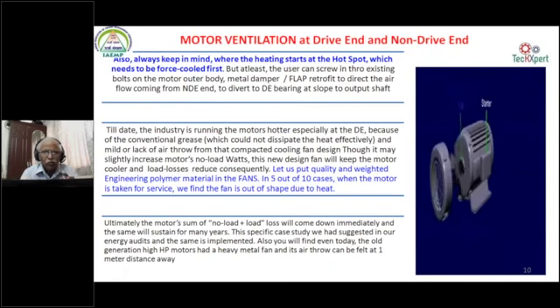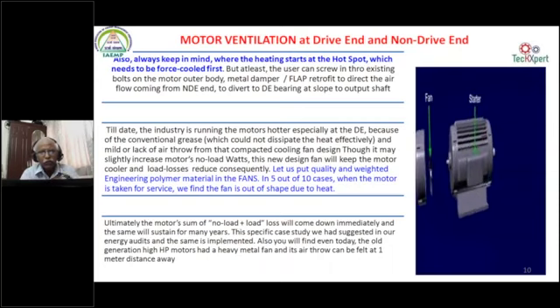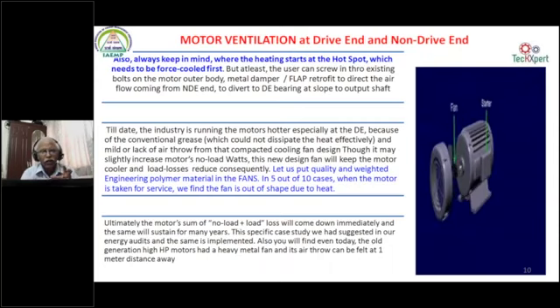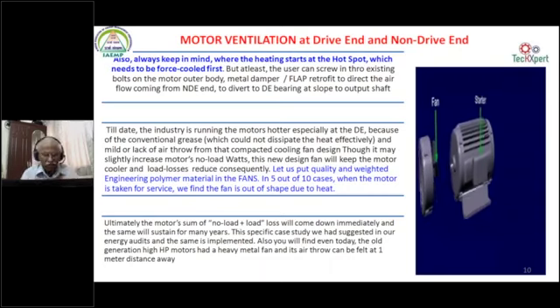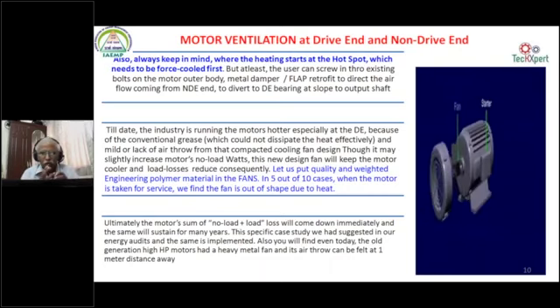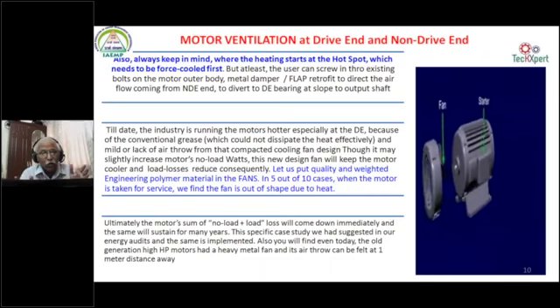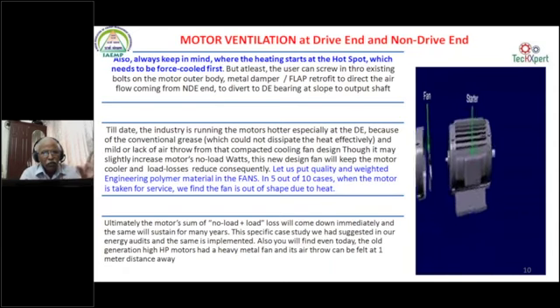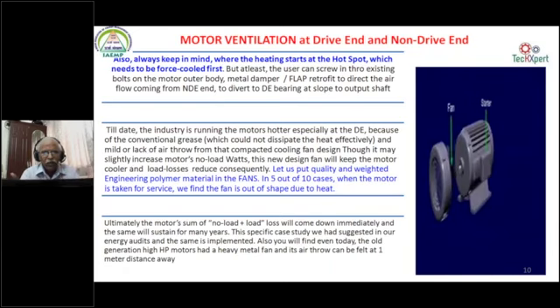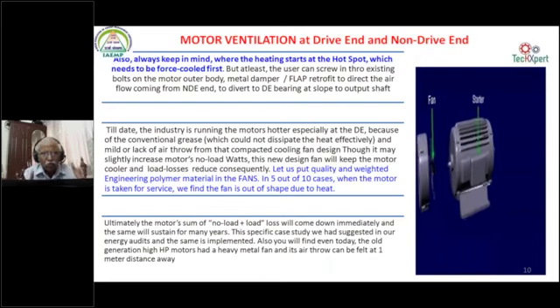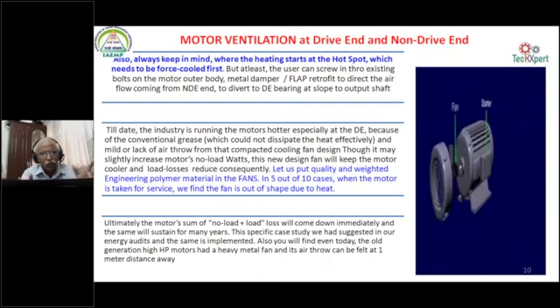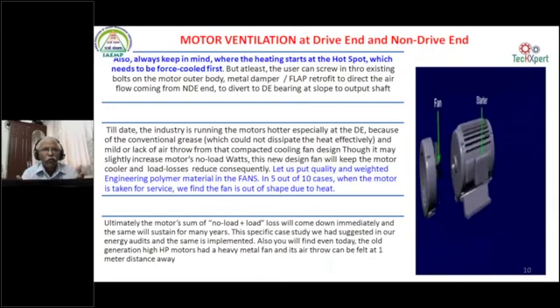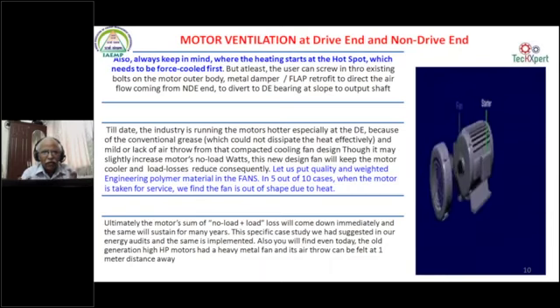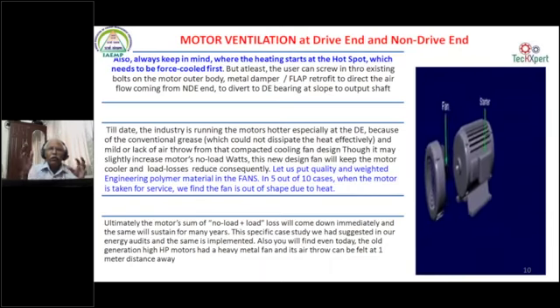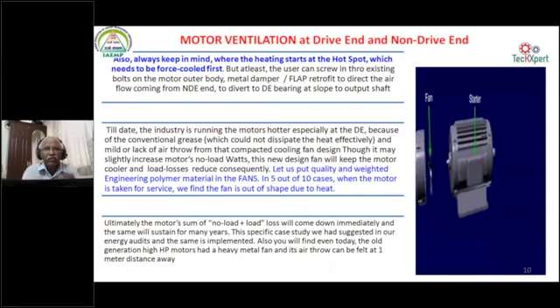Whatever the OEMs give, you discuss with the motor OEM, and then you see that active, sufficient ventilation from the motor fan cowl is delivered on the motor fins. So the no load and the load loss will definitely come down during the loading. See, in the first case we are putting a small fan, typically as given by the motor OEM, it will show no load loss as less. But when you are putting a bigger fan to suit your environment, automatically at the loading, the overall losses will come down, the motor heat is coming down.